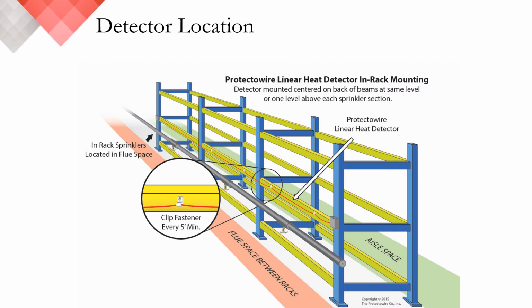A quick note for anyone designing or installing Protectowire or any other digital linear heat detector. If the detector is installed at a typical room temperature of 70 degrees Fahrenheit, which is 21 C, it is necessary to purposefully leave a bit of sag, or allow for the detector to slightly dip, in between fasteners. When the facility is finally chilled, the cable will contract, reducing the sag in between the fasteners. The amount of sag to be installed in between fasteners is directly related to the temperature at which the refrigerated or freezer warehouse is expected to operate.